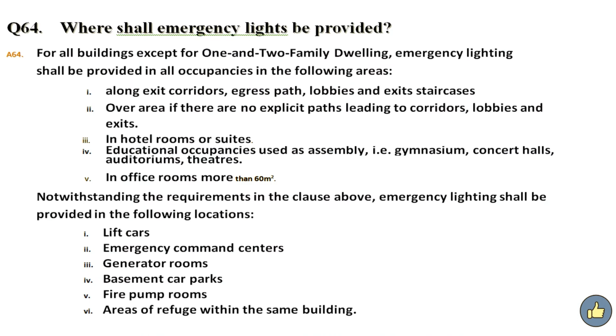Where should emergency lights be provided? Answer. For all buildings except for 1 and 2 family dwellings, emergency lighting shall be provided in all occupancies in the following areas. Number 1. Along exit doors, egress paths, lobbies and exit staircases. Number 2. Over areas where there are no explicit paths leading to corridors, lobbies and exits.